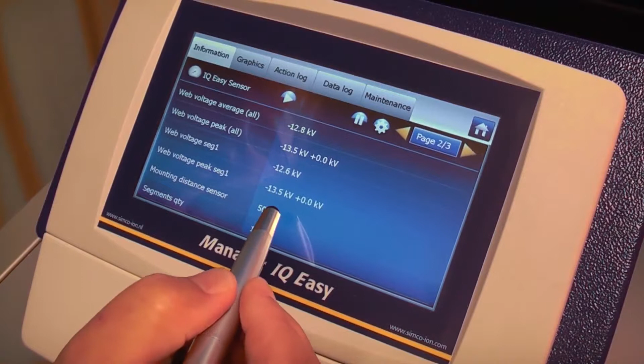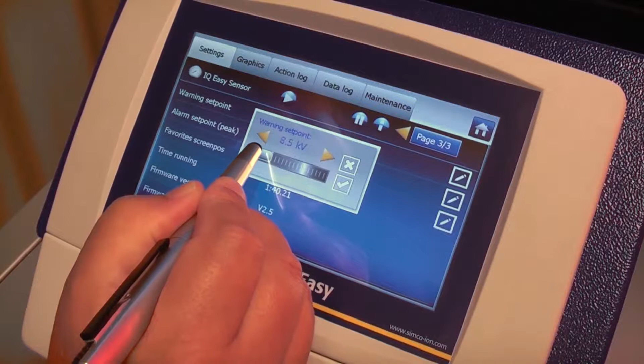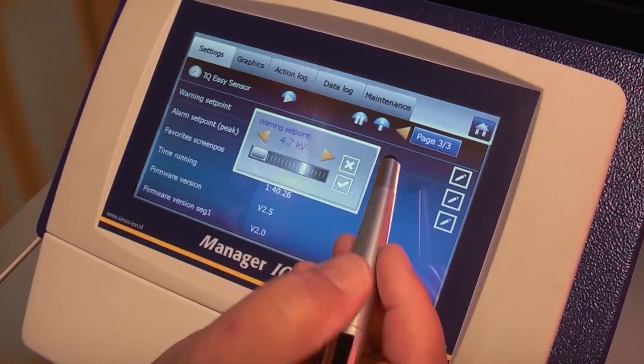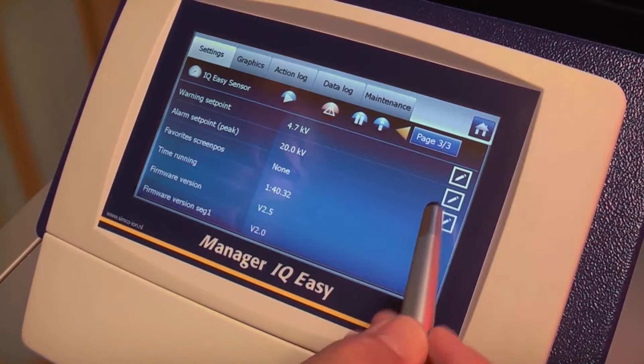On page 3, you can set a warning set point and an alarm set point. If we go back one screen, we can see it is fluctuating around 12.5, 13 kilovolts. So if I change these parameters by going into the settings screen, I can set the warning set point to a lower level, like for instance 4 kilovolts. And you immediately can see it is giving me a warning.